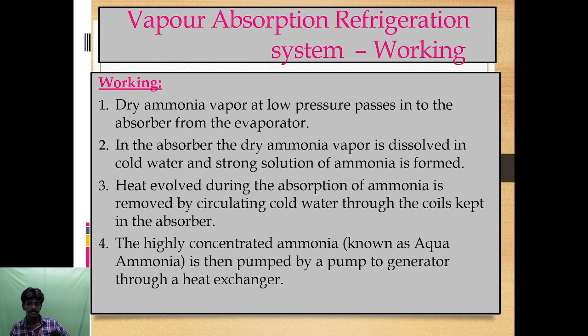The highly concentrated ammonia, known as aqua ammonia, is then pumped to the generator through a heat exchanger. In the heat exchanger, the strong ammonia solution is heated by the hot weak solution returning from the generator to the absorber. The heat source can be a burner, like solar, wood, anything. In the generator, the warm solution is further heated by steam coils, gas or electricity, and the ammonia vapor is driven out of the solution.